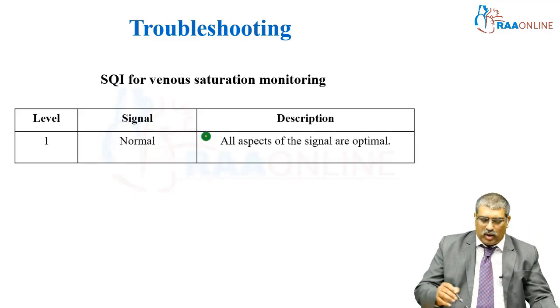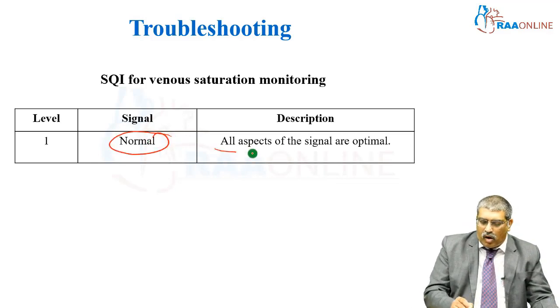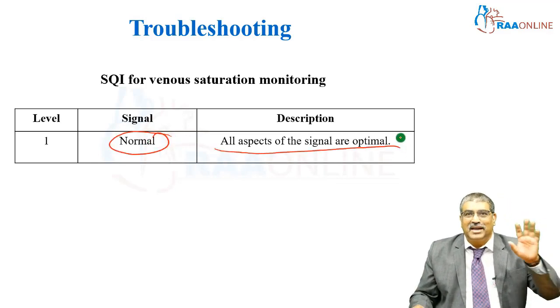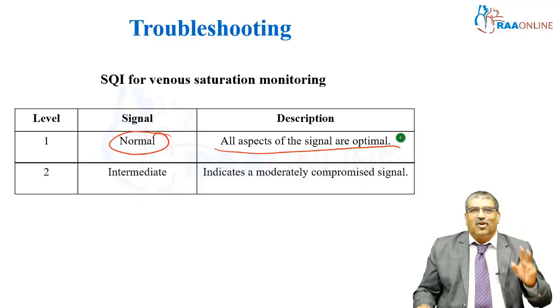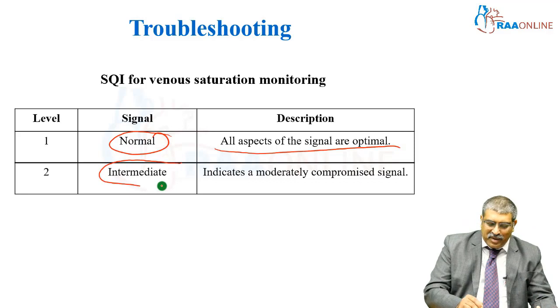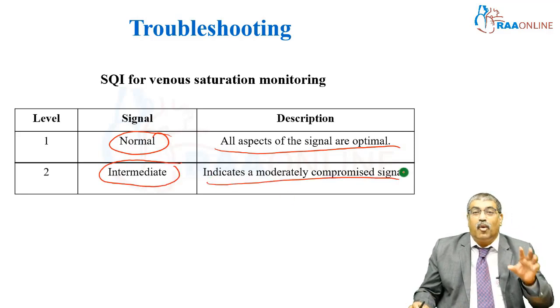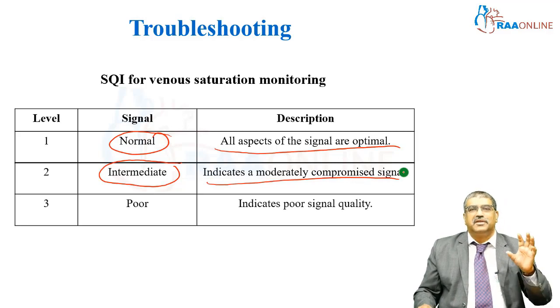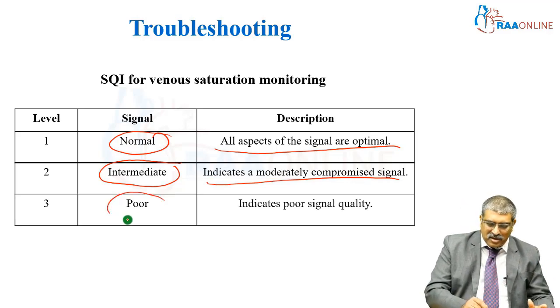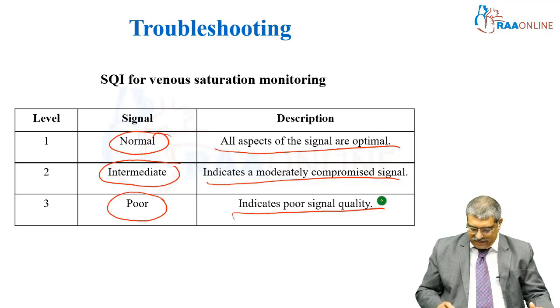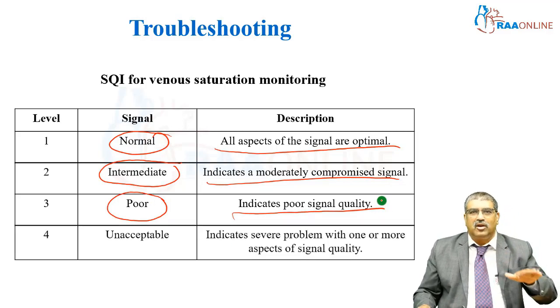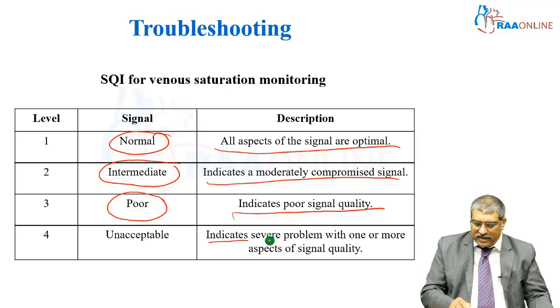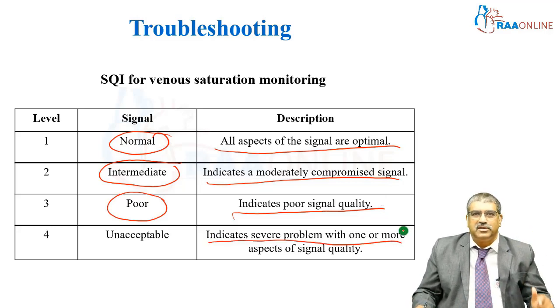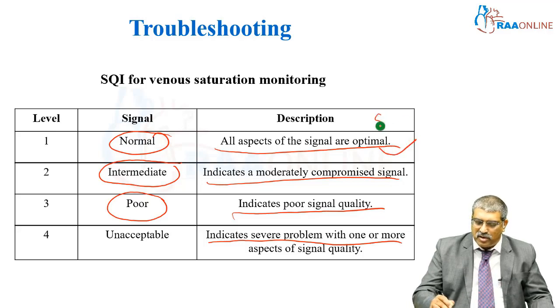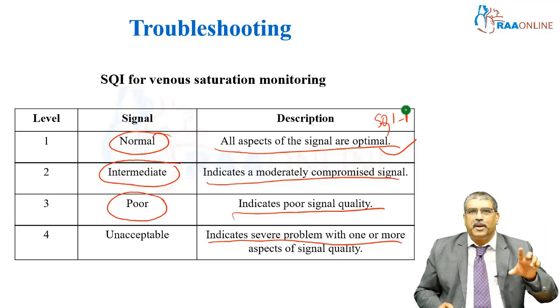If it is at level 1, the signal is normal, all aspects of signal are optimal and you will get a value. If the signal quality index is at level 2, it is an intermediate signal and it indicates a moderately compromised signal. If the signal quality index is 3, the signal is poor and it indicates poor quality signal. And finally, if the signal quality index is 4, it is unacceptable. It indicates severe problem with one or more aspects of signal quality. So, a signal quality index of 1 should always be there for a good digital display of the mixed venous oxygen saturation.